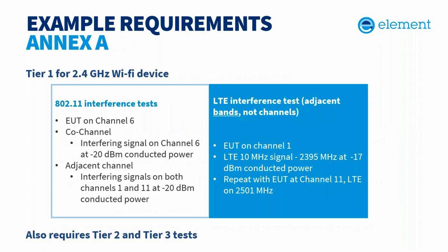In 63.27, Annex A is normative and provides specific guidance for the unintended signals in the setting of the EUT. For Wi-Fi, Tier 3 requires a single adjacent channel test with the EUT on channel 6 and interfering signals at 1 or 11. Tier 2 adds a co-channel test, so essentially the EUT is on channel 6 and an interfering signal is also on channel 6. Then Tier 1 requires all of these and also adds a test with both the adjacent channels and LTE adjacent bands. So the EUT is on channel 6 and interfering signals are on channels 1 and 11, and then the EUT is on channel 1 and an LTE signal is just out of that band.